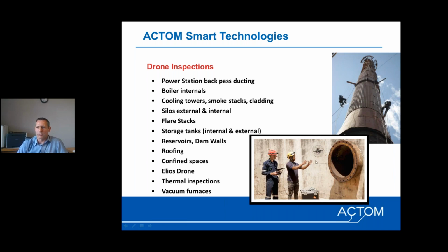The big advantage of doing inspections with a drone is, in the past, you would have had to erect scaffolding to do all of these inspections, which could take up to 2 or 3 weeks. With a drone, that inspection time can be cut down to within 24 hours - really a time-saving and cost-saving solution for the end customer. When the drone inspections are done, you can pinpoint very specific points where you need to do maintenance. Instead of putting scaffolding in your whole boiler, you could use the lineman and rope access to target specific areas where maintenance is required.